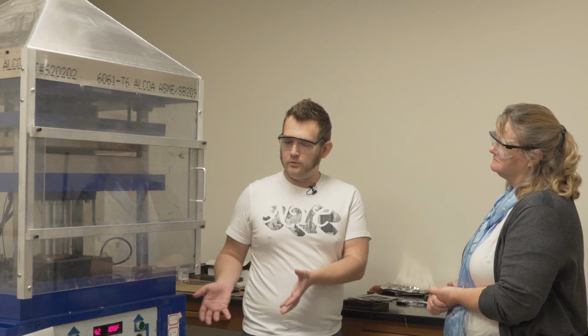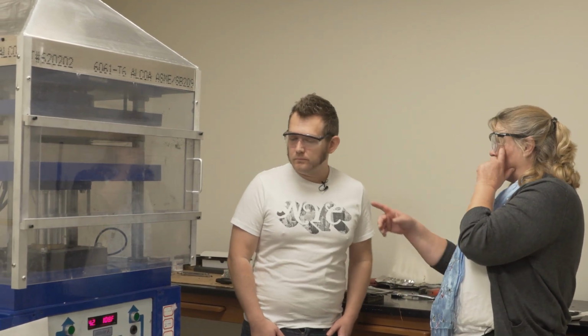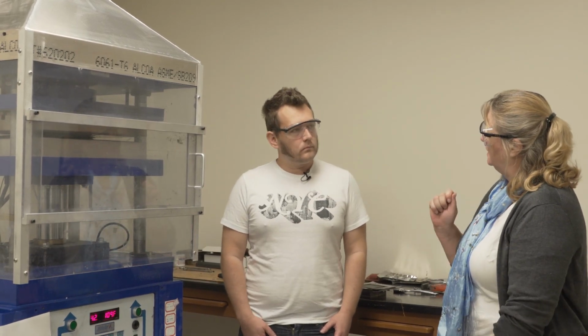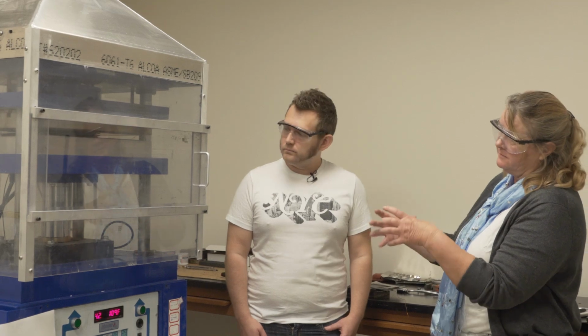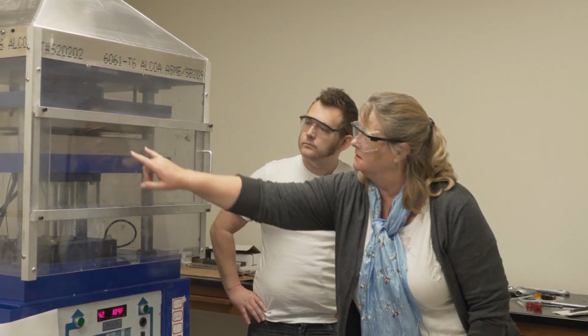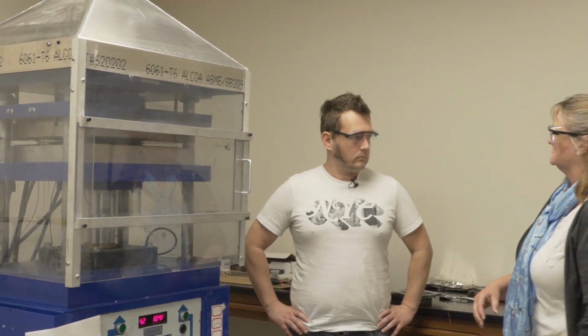That's fantastic. So can you tell me a little about how this machine works and turns sols into aerogels? It's basically a hydraulic hot press. We use compressed air with a pump that pumps up a cylinder below full of oil, and we apply pressure to one side. That pressure in the cylinder pushes on these platens, pushing them together to provide the force. These are commonly used for laminating things, where you want to heat something and then squeeze it down with high force. It's programmable, which is great — we start it up, leave, and come back 6 hours later and we've got our aerogel. Set it and forget it.